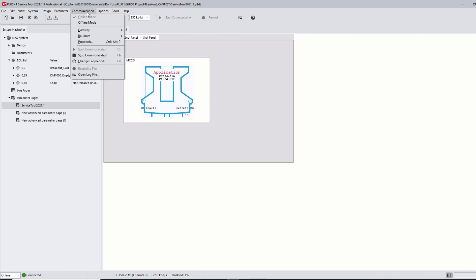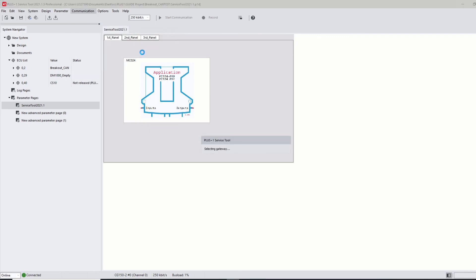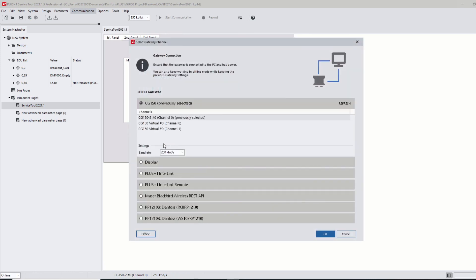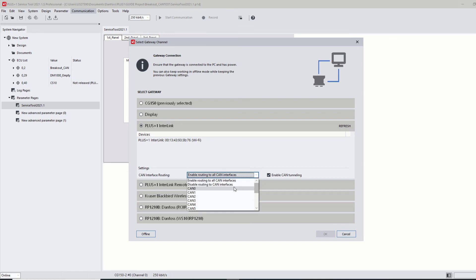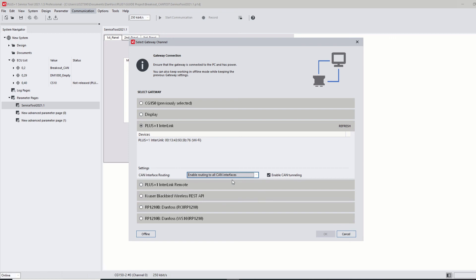After showing the advanced page improvements, I will move to the extended features like Plus One Interlink and remote gateway support. By default, routing to all CAN interfaces is enabled, meaning any Plus One device connected to the CAN interface of the remote gateway will be accessible in Plus One Service Tool. This functionality can be configured in the CAN interface routing before connecting to the device, where the user can enable single or all CAN ports of the Plus One Interlink gateway which should participate in routing of CAN messages. CAN tunneling is another gateway setting which can now be enabled or disabled from the gateway selection dialog to enable reception of CAN messages from the Plus One Interlink gateway. CAN tunneling needs to be enabled for CAN messages to be displayed in CAN monitor and to use CAN Explorer protocol.